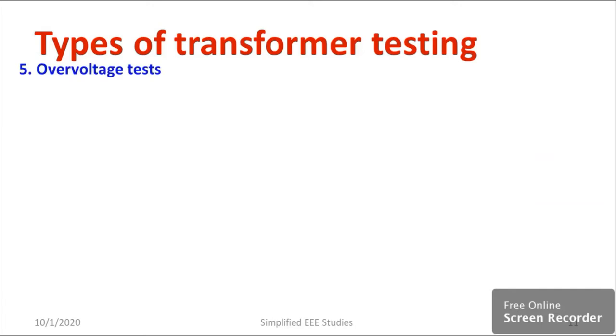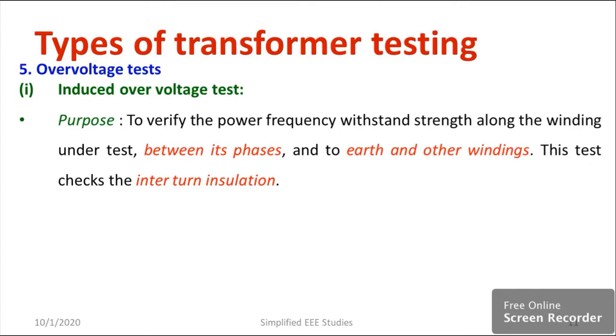Now I would like to discuss about the overvoltage test. There are two procedures: induced overvoltage test and partial discharge test. The induced overvoltage test is conducted to verify the power frequency withstand strength of the winding under test, between its phases and to earth and other windings. This test checks the inter-turn insulation.